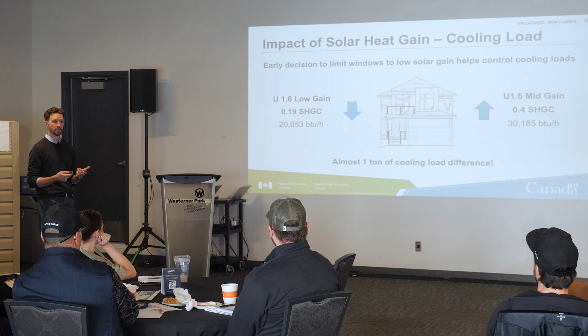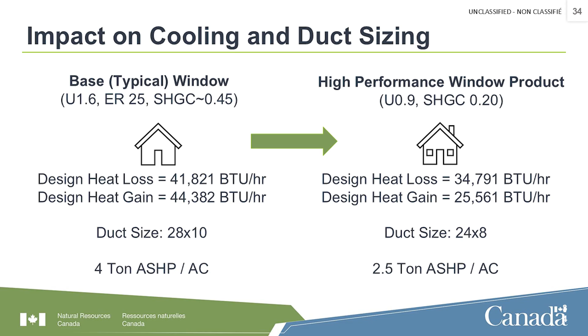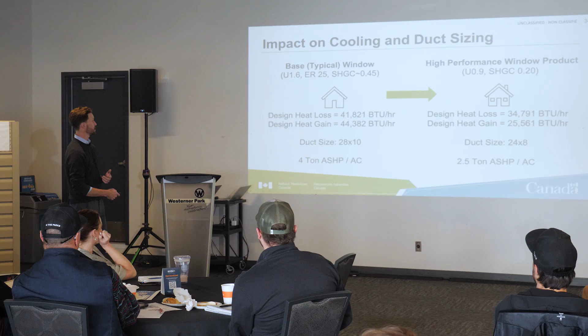When we move from a 1.6 with a moderate solar heat gain to a better U value and a better or lower solar heat gain, you actually have an opportunity to save on the size of the ducts. So in this case, because we've improved both the U value and the solar heat gain value, we're moving the needle on both the heating load and the cooling load, stated here as design heat loss and design heat gain, moving them down. And this allows you to go from a 4-ton air source heat pump to a 2.5-ton air source heat pump. But maybe more interesting for those of you that might want to consider a finished basement rec room for your clients, going from a duct size plenum of 28 by 10 down to 24 by 8. Something smaller that gives you a couple extra inches of ceiling height to work with. So lots of ripple effects as we make these decisions.